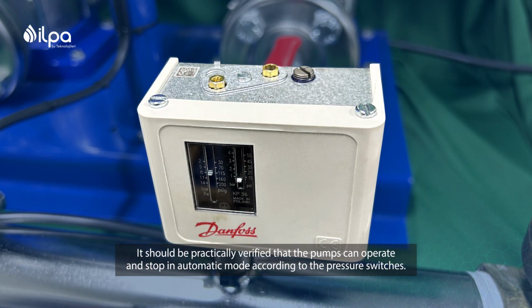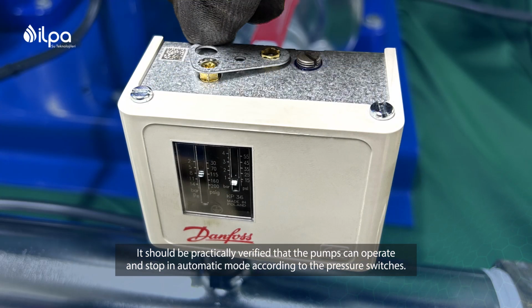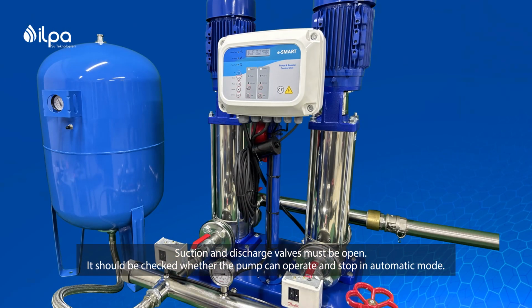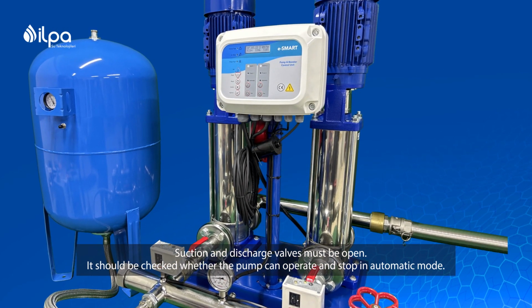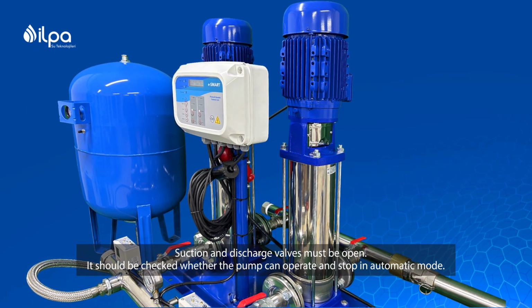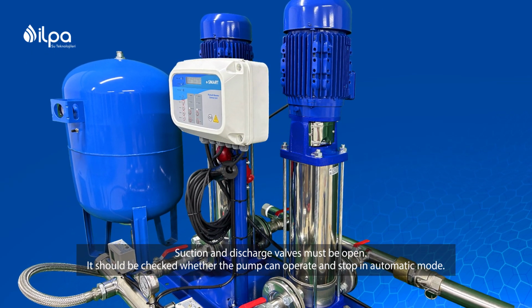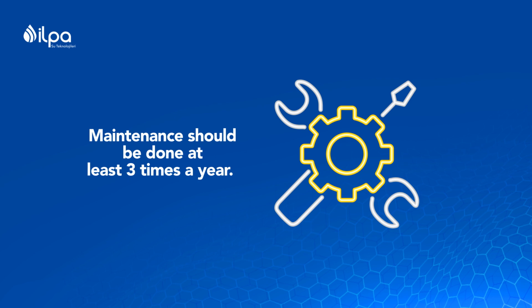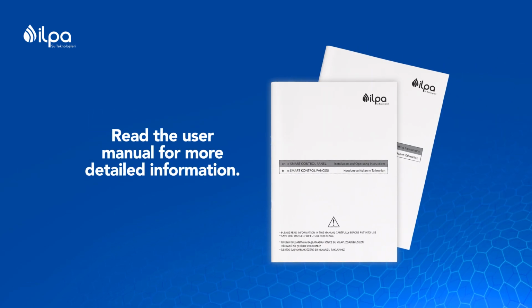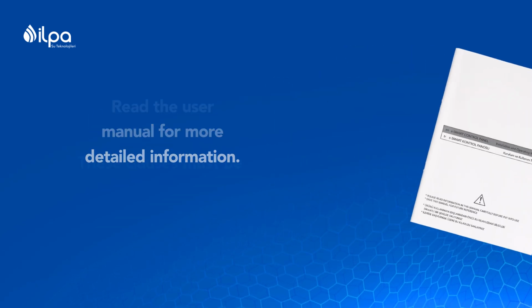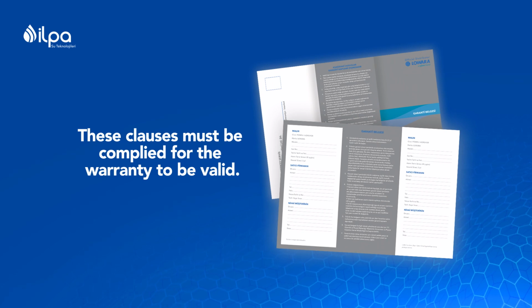It should be practically verified that the pumps can operate and stop in automatic mode according to the pressure switches. Suction and discharge valves must be open. It should be checked whether the pump can operate and stop in automatic mode. Maintenance should be done at least 3 times a year. Read the user manual for more detailed information. These clauses must be complied with for the warranty to be valid.